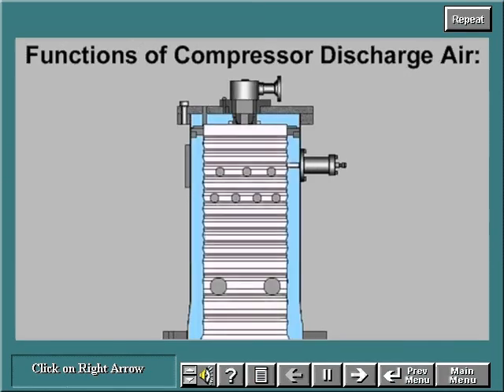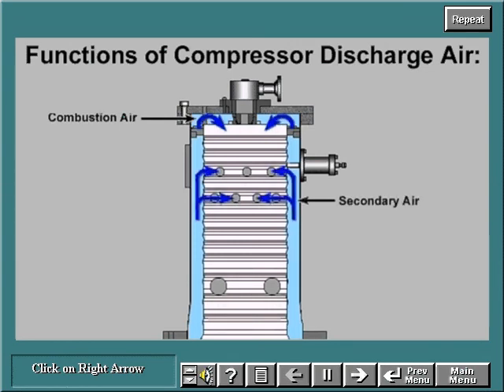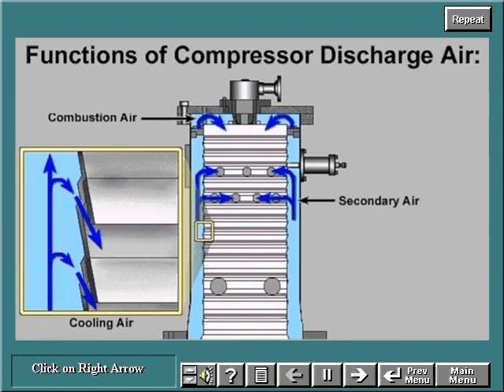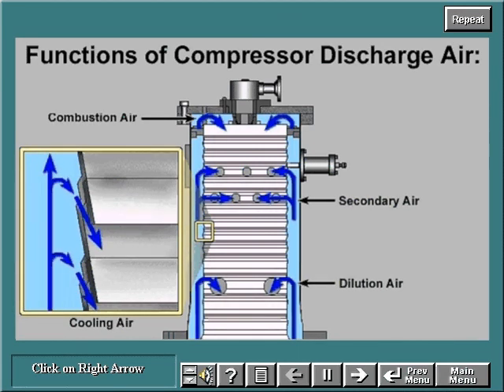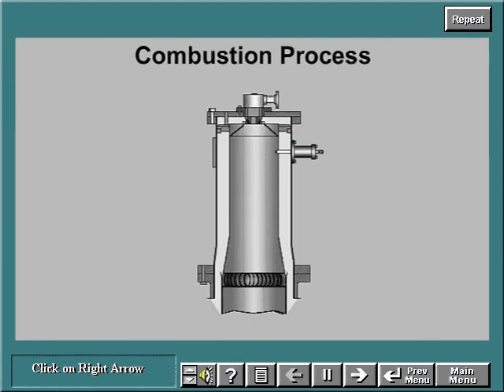The compressor discharge air has four basic functions. It is used as combustion air — primary air — to achieve the proper fuel-air ratio. It is used as secondary air to cool and stabilize the flame. It is used as cooling air to provide a continuous cooling film along the external and internal surfaces of the liner. And it is used as dilution air downstream of the primary combustion area to reduce the gas temperature and preserve the life of the hot gas path components.